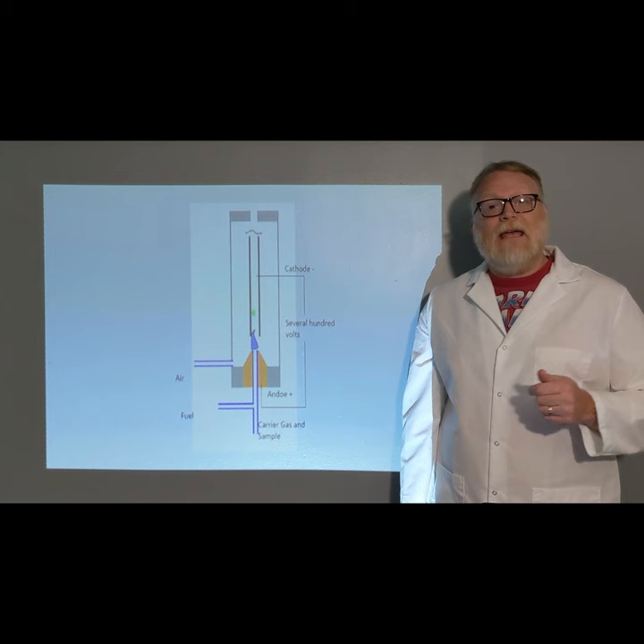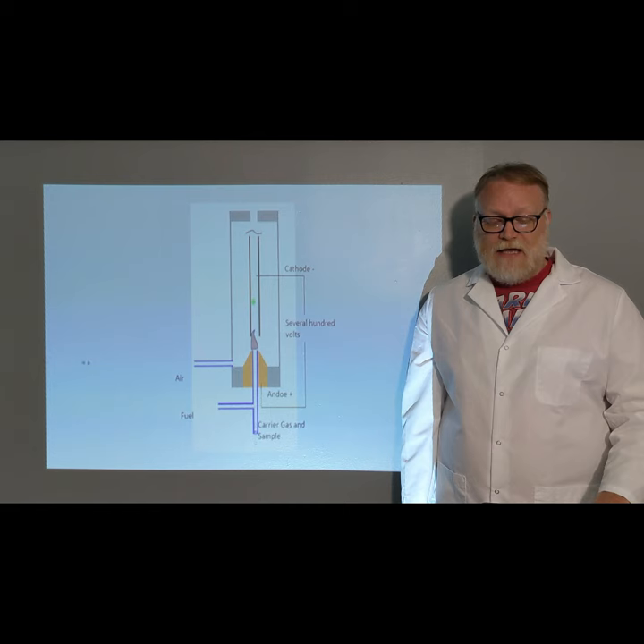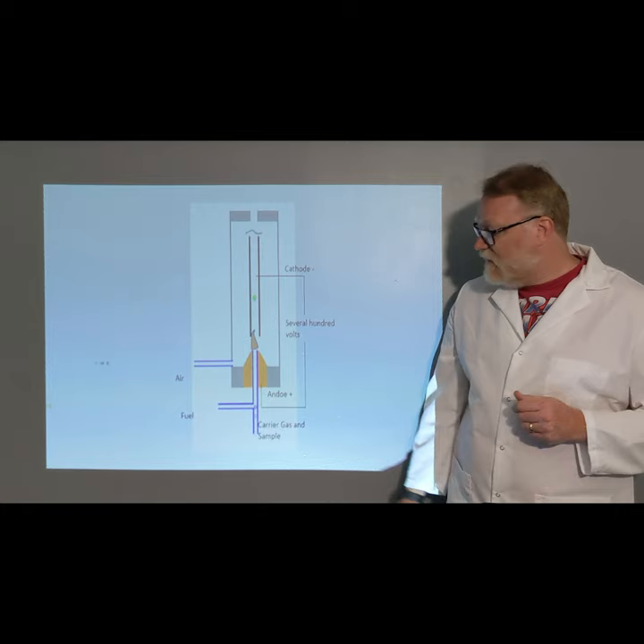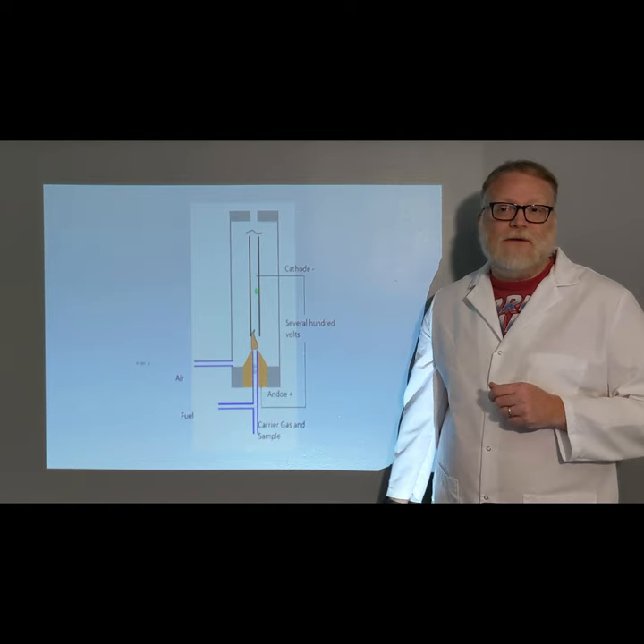This introduction of your sample into the jet is crucial in getting good results. If the column isn't placed just right, your results will suffer. If you've got a broken end on your column, you could get vortexing, which will allow for noisy peaks.